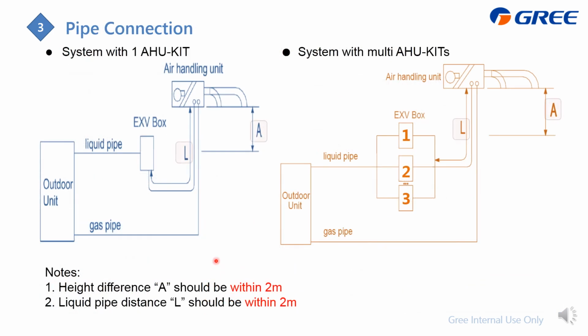Here is the requirement for the piping, which is from the EXV box to the AHU. This L and A, which is the height drop for the A, and the length, the distance for the L, it should be within 2 meters, which means this EXV box should be close to the AHU, either for the one AHU or multi AHU.